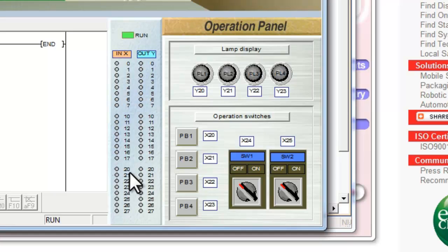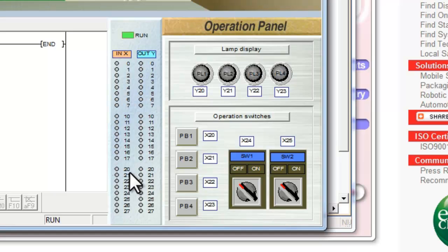For L series, one other point to make is that every L series comes with built-in inputs and outputs. In an L series system, X0 through XF are assigned to the CPU, as well as Y0 through Y7. Y8 through YF are not used, however they are still occupied. So if you do connect an output module onto an L series, the addressing will start after YF.